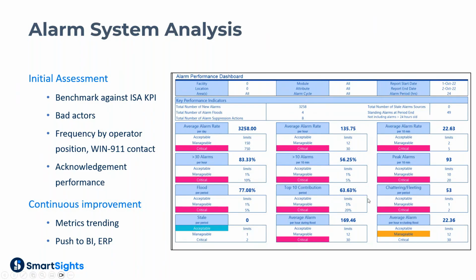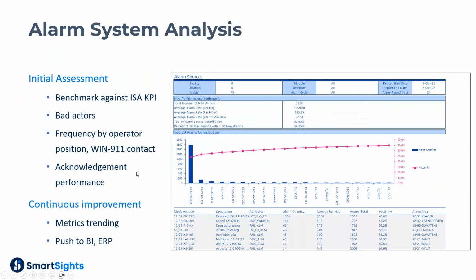Those are the ones I really want to take a very close look at to see if they're actually programmed effectively. This tool allows you to drill down behind this number and see, for example, a Pareto analysis of what's making up that top 10. Even within the top 10, there's really one specific condition that's happening a little more than once a minute, so it's a constantly chattering alarm.